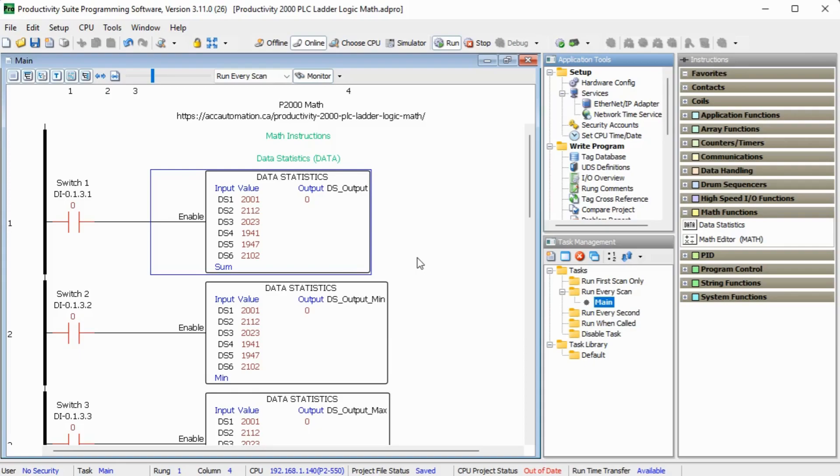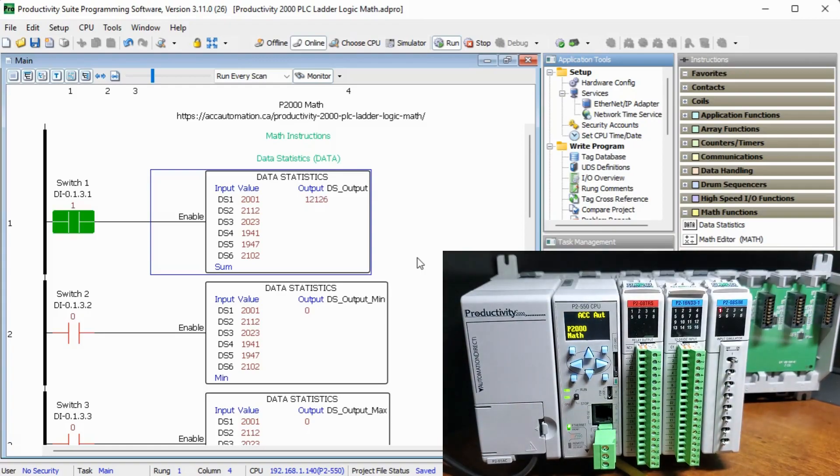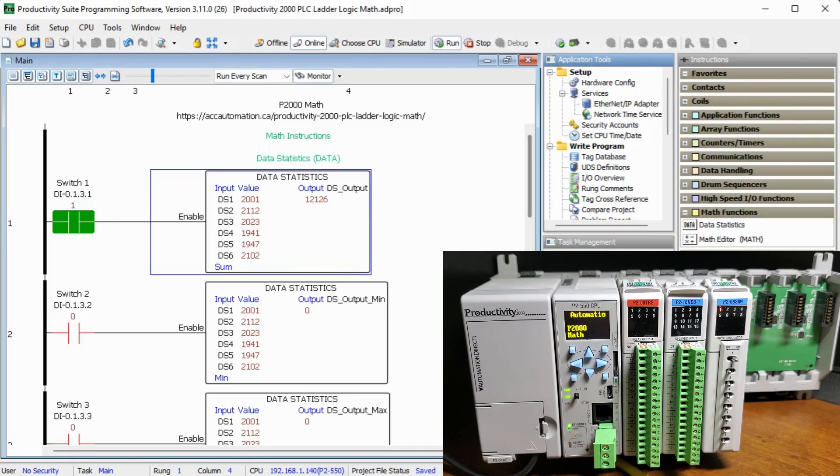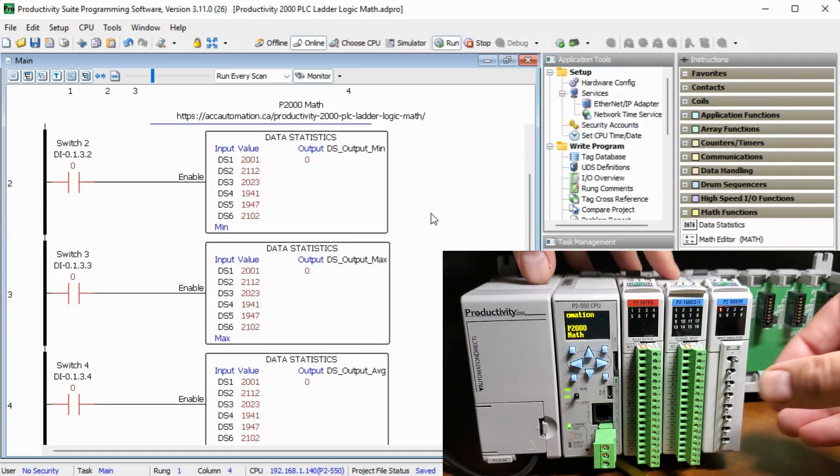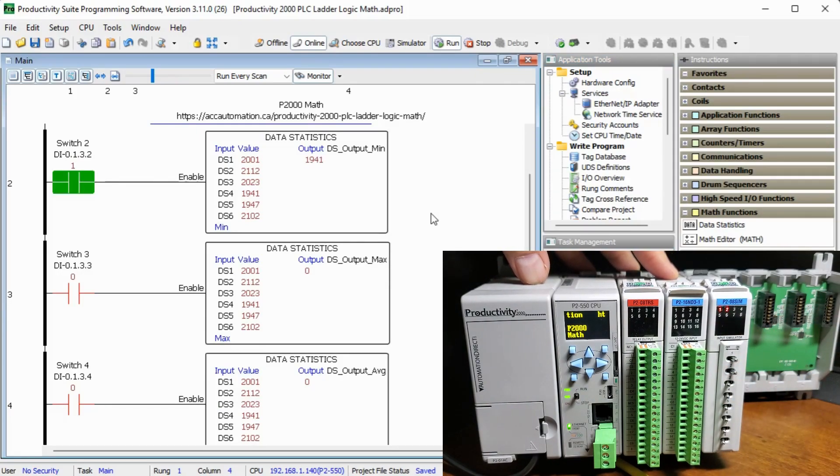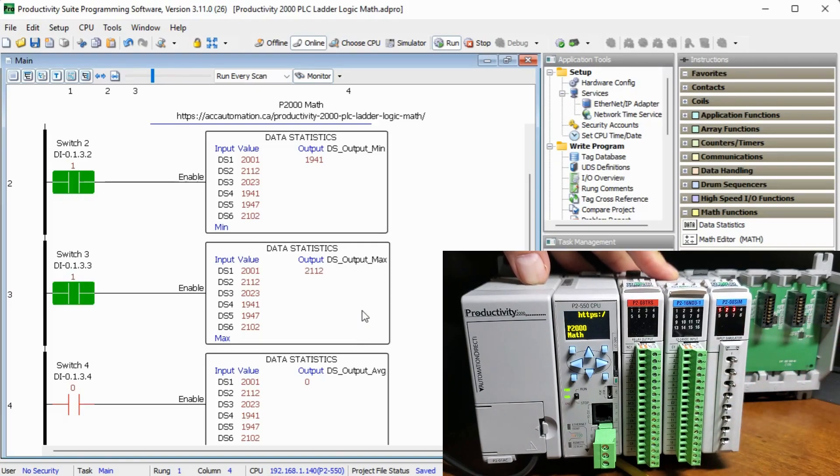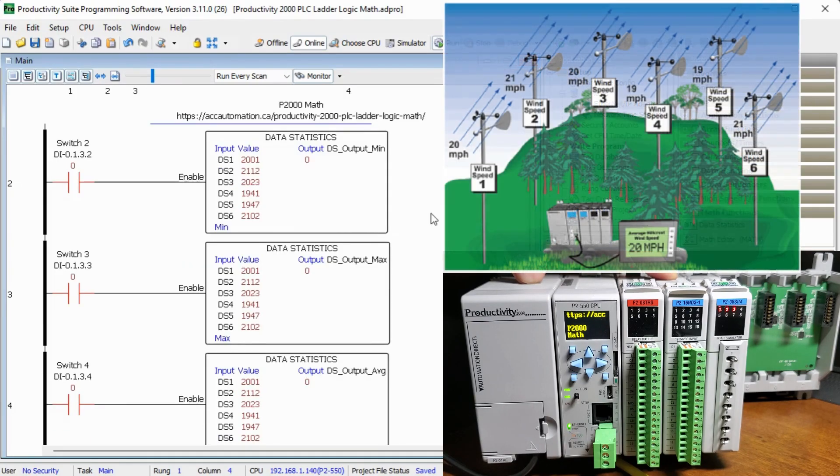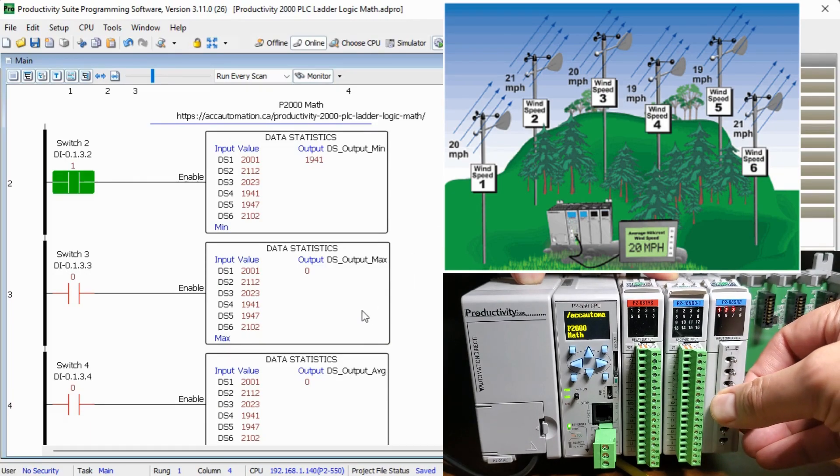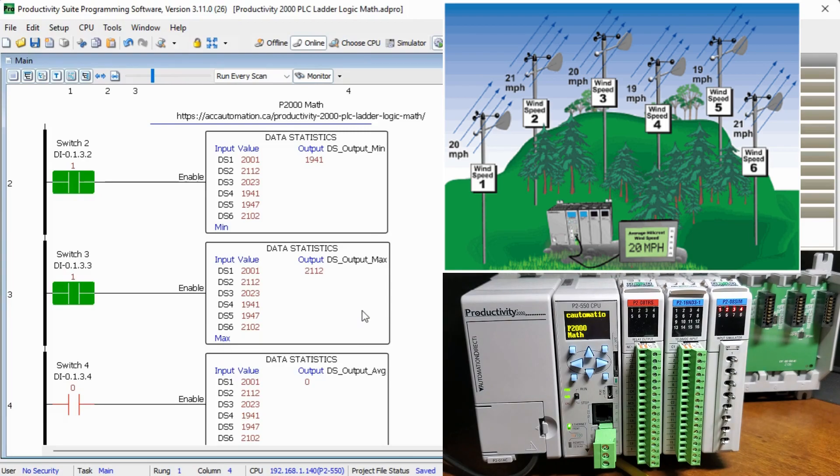Switch one will enable our first data statistics instruction. This will be used to sum or add the numbers together. Copy and paste are then used to copy the first one three more times, making the following changes. Switch number two will find the minimum value of the tags ds1 to ds6. Switch three will find the maximum value of the tags ds1 to ds6. And then our application for the average wind speed will be calculated using switch number four. Switch four will find the average value of the tags ds1 to ds6.